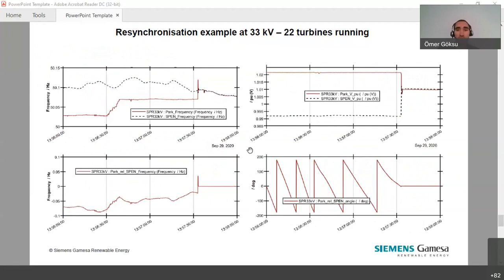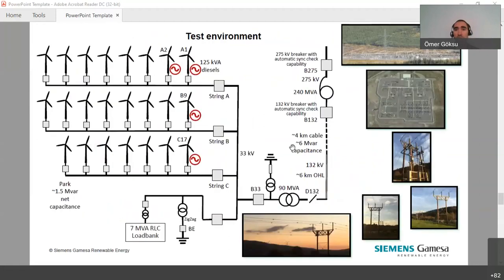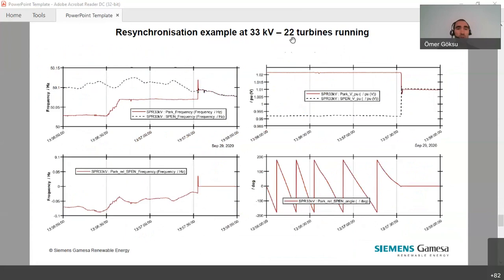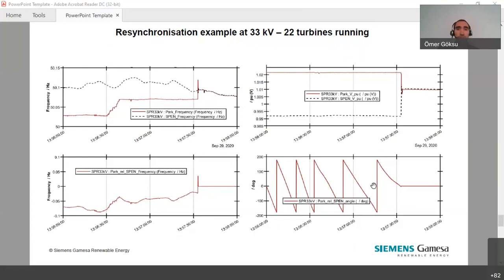If you are curious, let me go back to the network again. It was resynchronization at 33 kV with B33, I think it should be. And almost all turbines except one were running. And first the frequency reference was increased to bring it towards the main grid frequency. And at this time you can see the synchronization is done. And yeah, the frequency difference is zero then, and the voltage is also matching, and then you can see the phase angle here.